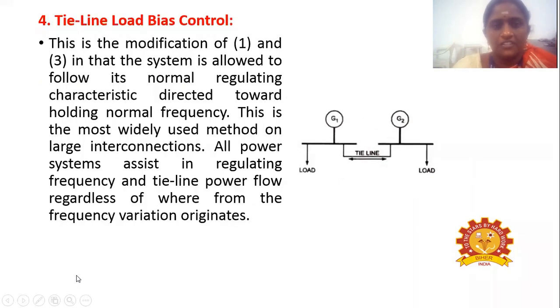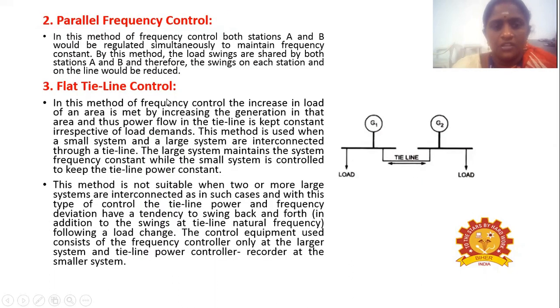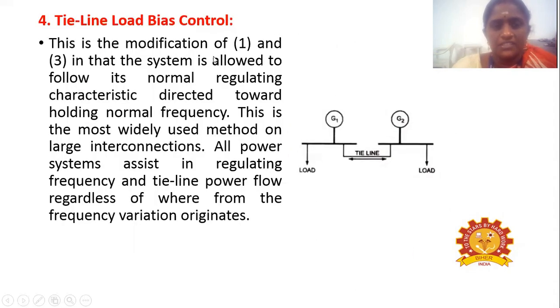The last method of load frequency control is tie line load bias control. This is a modification of flat frequency control and flat tie line control. In this system, the system is allowed to follow its normal regulating characteristics directed towards holding the normal frequency. So each and every generator has to follow the normal regulating characteristics. This is the most widely used method on large interconnections. In this, all power systems assist in regulating the frequency and the tie line power flow regardless of where the frequency variation originates. Whether the deviation occurs in station A or station B, both generators and the tie line powers are regulated. So this method is called tie line load bias.